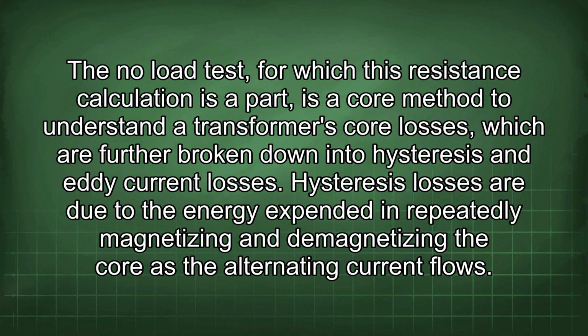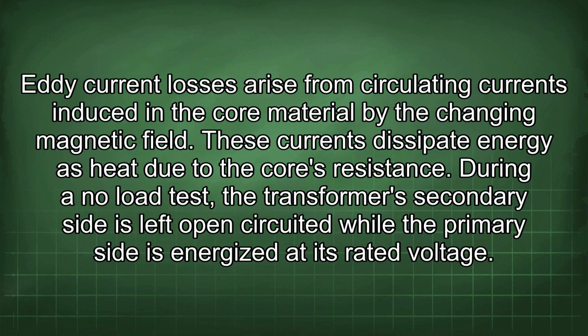systems. The no-load test, of which this resistance calculation is a part, is a core method to understand a transformer's core losses, which are further broken down into hysteresis and eddy current losses. Hysteresis losses are due to the energy expended in repeatedly magnetizing and demagnetizing the core as the alternating current flows. Eddy current losses arise from circulating currents induced in the core material by the changing magnetic field. These currents dissipate energy as heat due to the core's resistance.